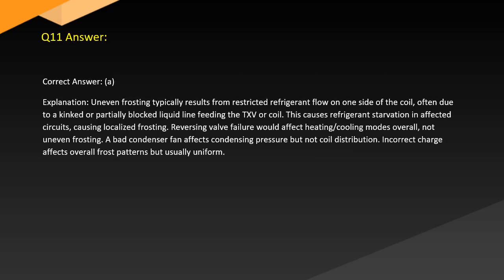Answer. Correct answer: A. Explanation. Uneven frosting typically results from restricted refrigerant flow on one side of a coil, often due to a kinked or partially blocked liquid line feeding the TXV or coil. This causes refrigerant starvation in affected circuits, causing localized frosting. Reversing valve failure would affect heating-cooling modes overall, not uneven frosting. A bad condenser fan affects condensing pressure but not coil distribution. Incorrect charge affects overall frost patterns, but usually uniformly.